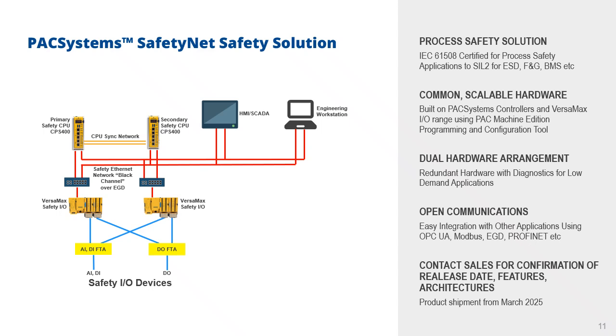We have an Ethernet network over which we're running our Ethernet Global Data protocol, but that's configured as a so-called black channel, which means we're controlling the impact of the safety network. The benefit of that is it means you can use any components on that safety network. They don't need to be, for example, dedicated switches. We're then using Versamax for our safety I/O, and then the I/O is duplicated, and then we use what we call field terminal assemblies or FTAs, which give us the link to the safety I/O devices.